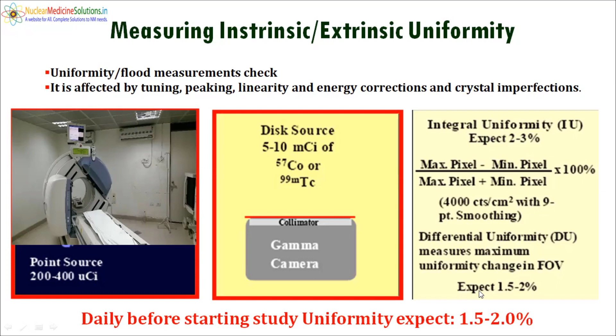Or we can use a flood source of cobalt 57 or technetium 99m to measure the extrinsic uniformity, that is with the collimator, and keep this flood source on the surface of the collimator while measuring the extrinsic uniformity. And then after acquiring the data, you can calculate the integral uniformity and the differential uniformity. Integral uniformity should not be more than 2 to 3%, and the differential uniformity should not be more than 1.5 to 2%.